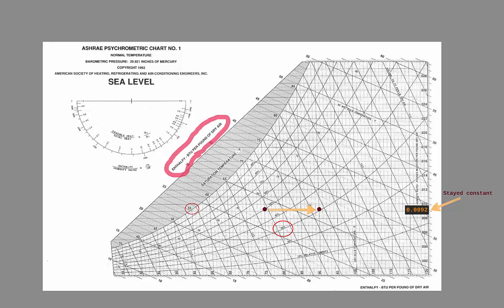We have provided several examples of how temperature can be measured. We have also provided some examples of how moisture content, whether it be relative humidity or the dew point temperature, can be measured. Based off the psychrometric chart, if you know two properties and assume a pressure, you will be able to determine the enthalpy of the air being measured. That is what enthalpy sensors do. They have to perform two such measurements, and then use that information in an internal lookup table or by solving some convoluted equation relating all the properties to provide the enthalpy reading.